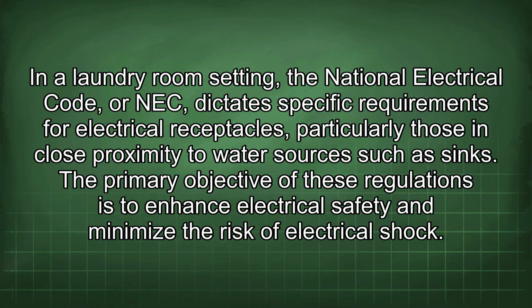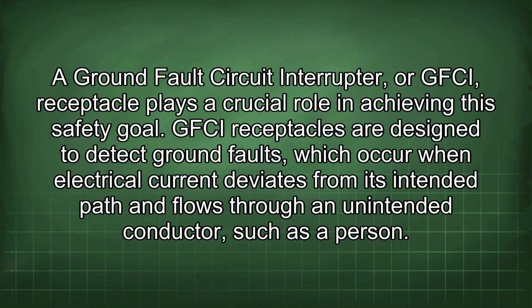In a laundry room setting, the National Electrical Code, or NEC, dictates specific requirements for electrical receptacles, particularly those in close proximity to water sources such as sinks. The primary objective of these regulations is to enhance electrical safety and minimize the risk of electrical shock. A ground fault circuit interrupter, or GFCI, receptacle plays a crucial role in achieving this safety goal.